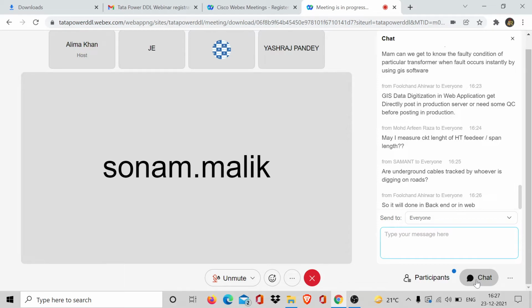Are underground cables tracked by whoever is digging on roads? There is a fault locating crew in Tata Power DDL, which uses GPR, that is ground penetrating radar, and other such devices which can track the underground cable. And now we have DGPS, that is DGNSS, in GIS, through which we get the exact coordinates of the cable. When we want to search for an underground cable, we take the rover to the site, and we can go to exactly the same spot again and track it.